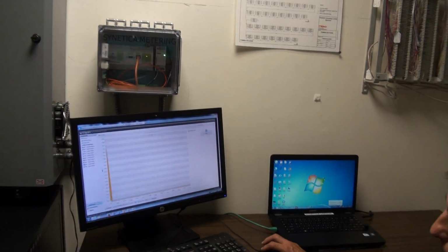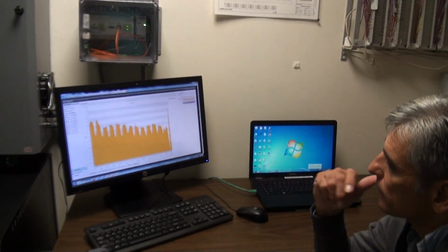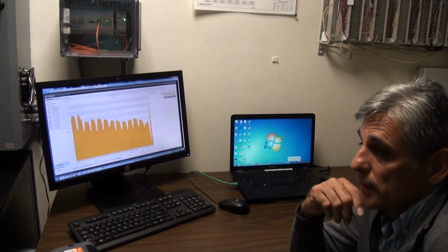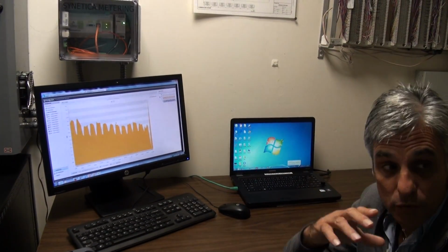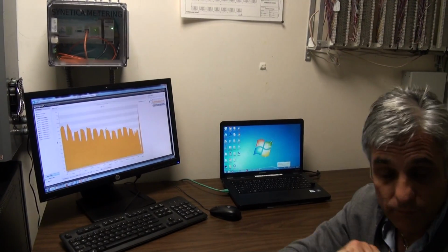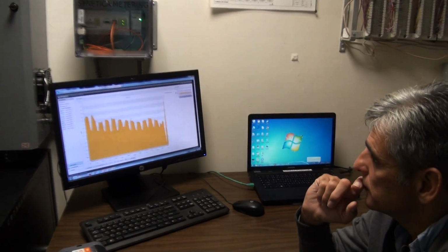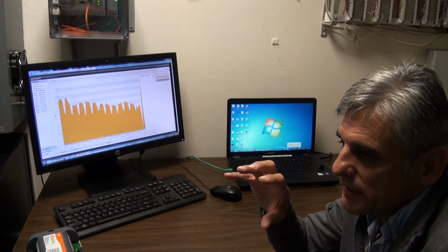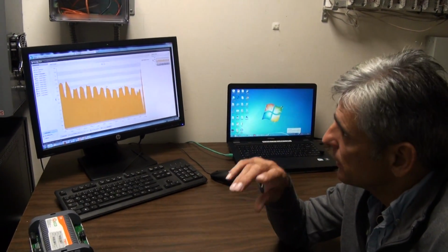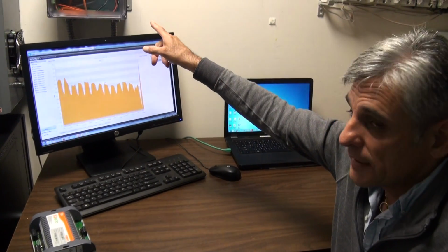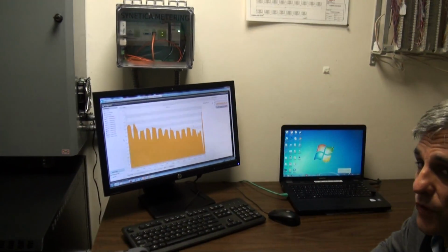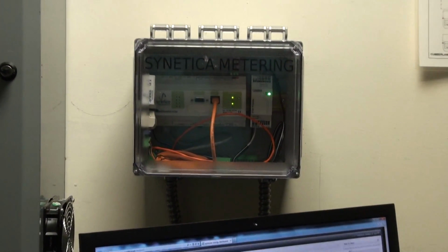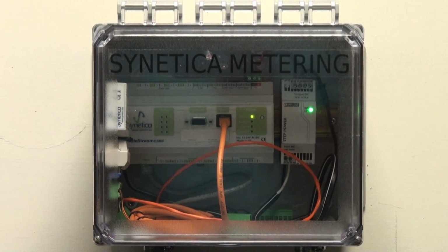With this metering system, what we have is 72 wireless meters connected into all the distribution panels. We're going to see those in a second. And basically what happens is all the data from each meter via repeaters streams into this data logger, which is connected directly onto the internet. All the information is stored off-site. It's actually stored off-site in the UK at the moment.